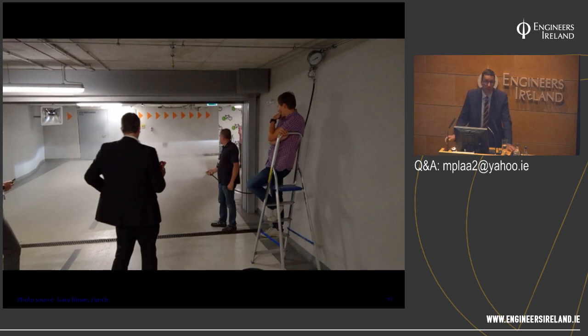I'm there late at night testing this system, and some of them took over 3.5 minutes to deliver water to the hydraulically most remote point. So bear in mind, we could have a car on fire and we're waiting 3.5 minutes for water. This system is currently being modified by the installer who have admitted fault on this system. In a system like that, what would the typical cause of that be? Is it just too long pipe runs, or?